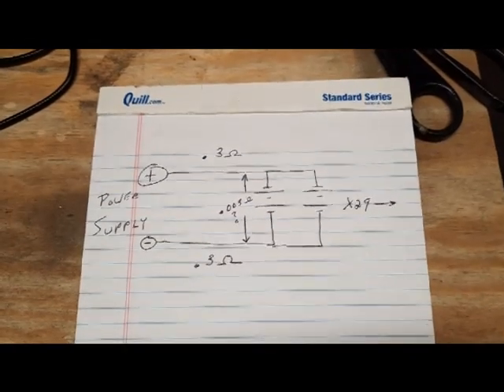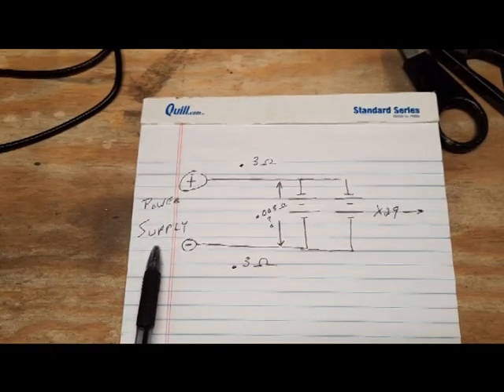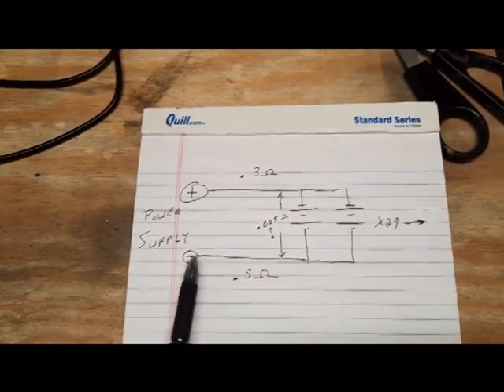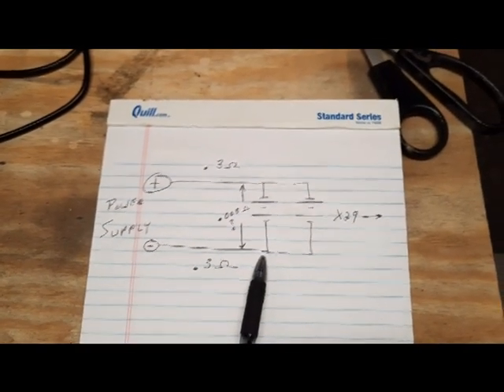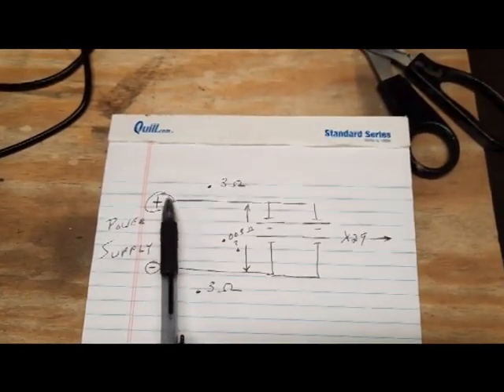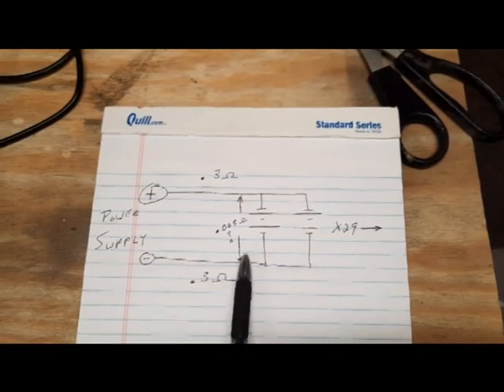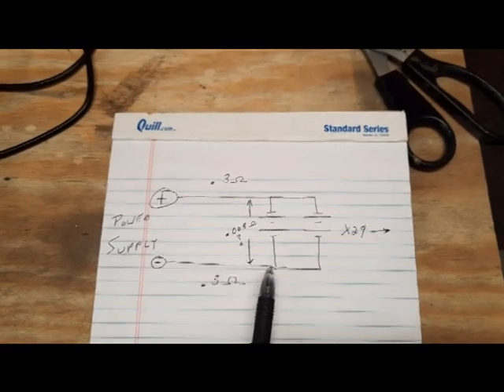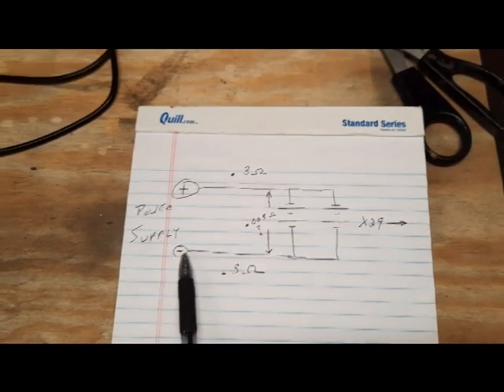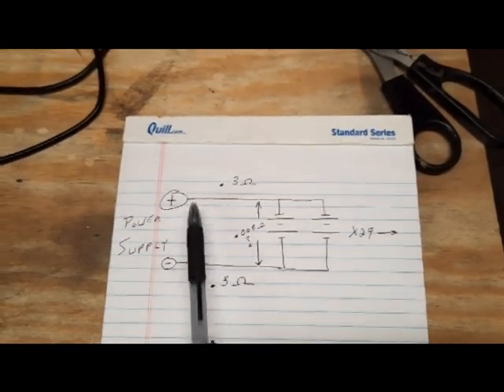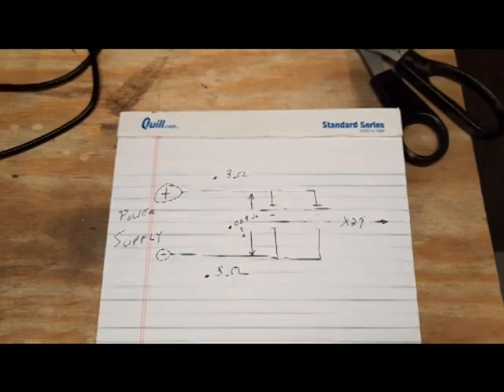So this is the result of all that higher mathematics. We have a power supply with a given voltage. It doesn't matter what it is. Going through a test lead with 0.3 ohms resistance, another test lead with 0.3 ohms resistance, and the internal resistance of 29 batteries in parallel, which is somewhere near spit. Bottom line is when you're tracking voltage drop, you're going to drop a lot here, and you're going to drop a lot here, and you're going to drop almost nothing here.